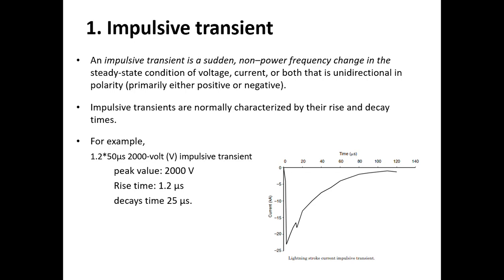Impulsive transients are normally characterized by their rise and decay times. For example, 1.2 by 50 microseconds, 2000 volt. The peak value is 2000 volt, the rise time is 1.2 microseconds and the decay time is 50 microseconds. All these are impulsive transients. Many times you get impulsive transients when a lightning stroke happens. A lightning stroke is a channel from cloud to ground, and because of that you get a higher voltage, which in short is called an impulsive transient.